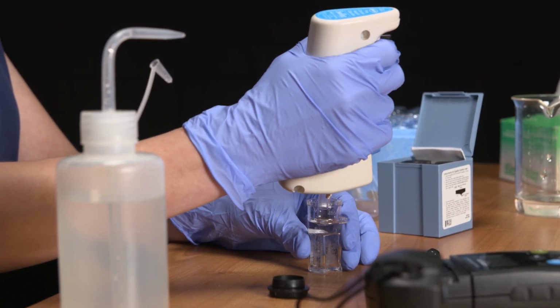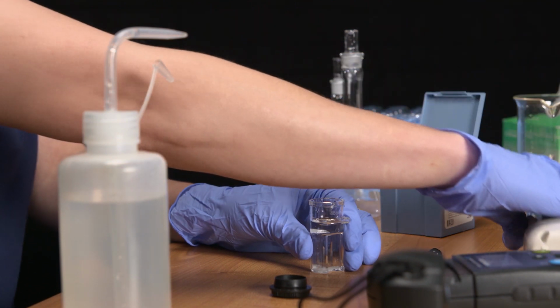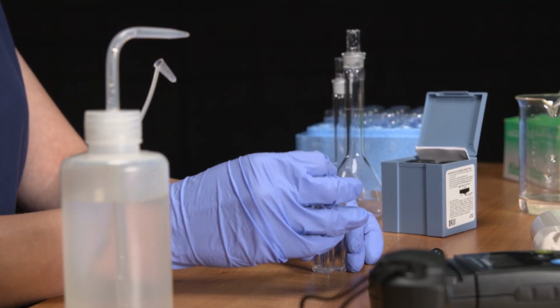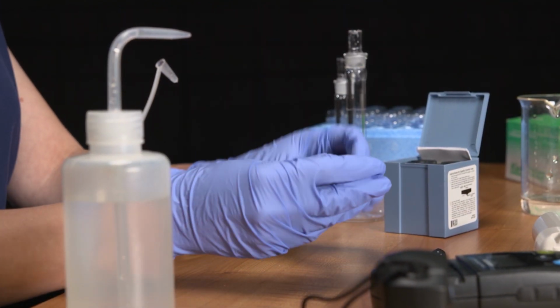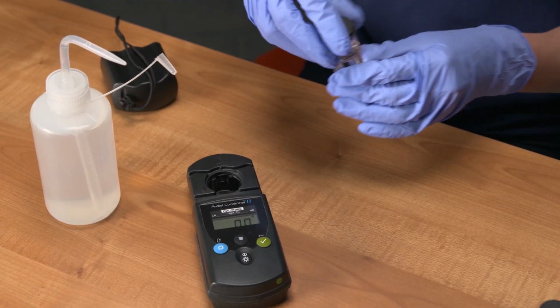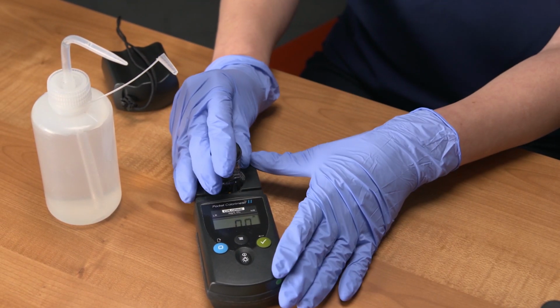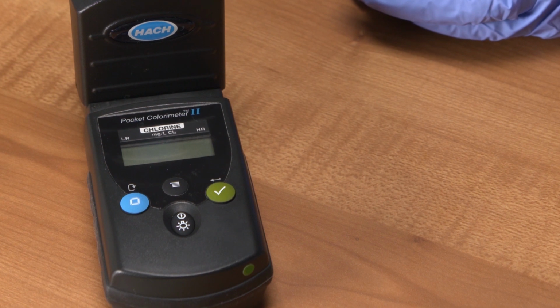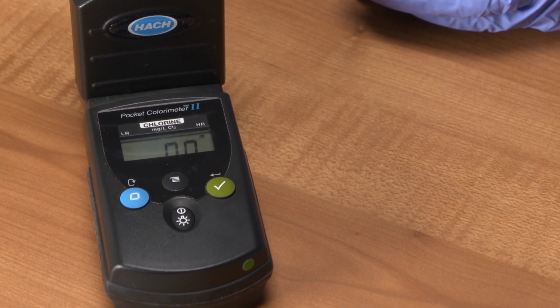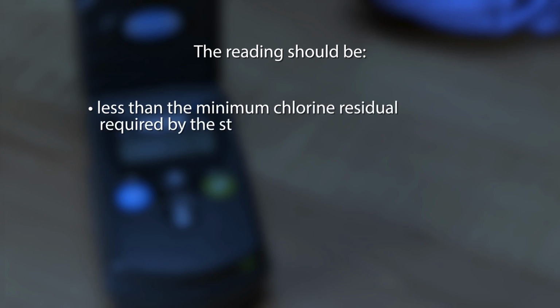We then take our reagent and add it. We mix the reagent by placing the cap on the vial and slowly inverting to mix. Next, we place the vial back in the colorimeter and take another reading.